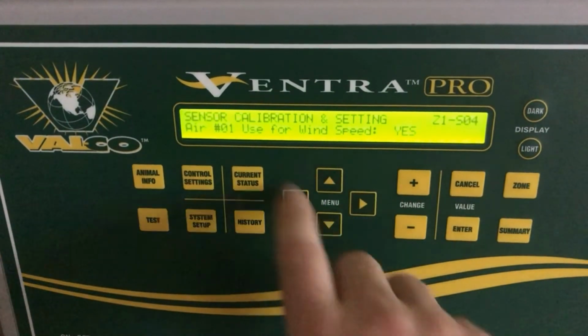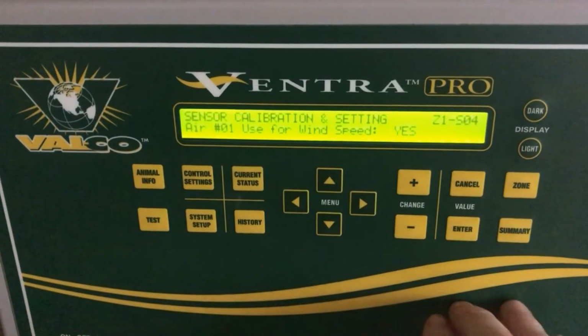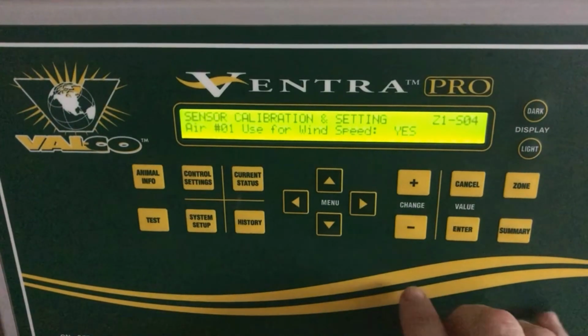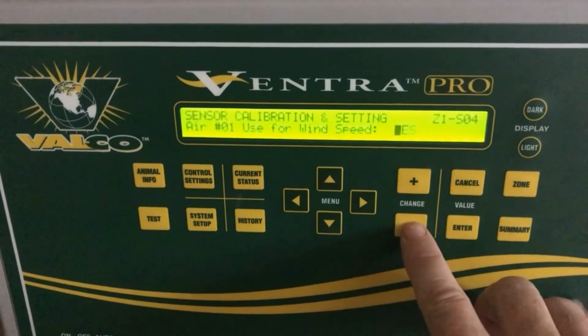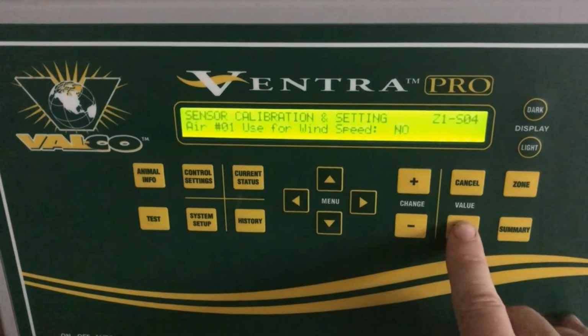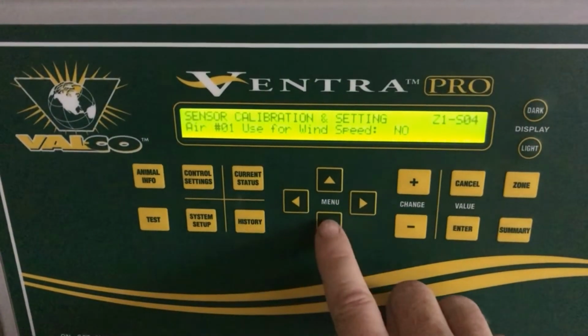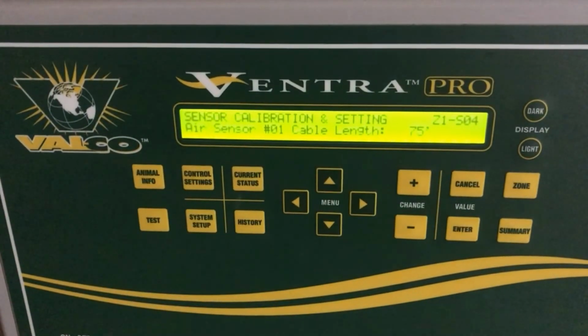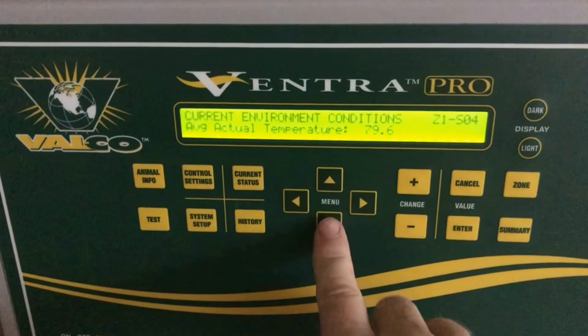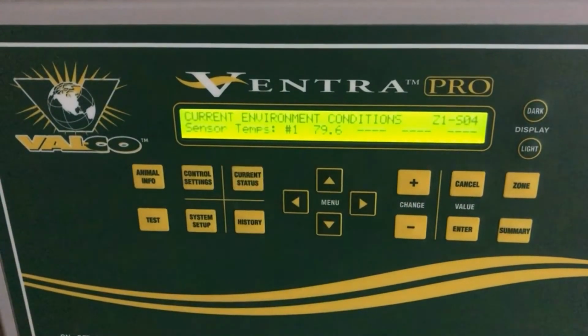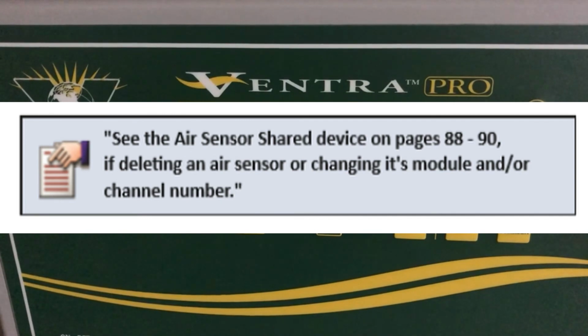Menu arrow down again, and we tell the controller if this temperature sensor also uses wind speed. In this case, no, it does not, so we change it to no, press Enter, and we have now set our temperature settings. We now have the number 1 temperature sensor programmed into our Ventra Pro.